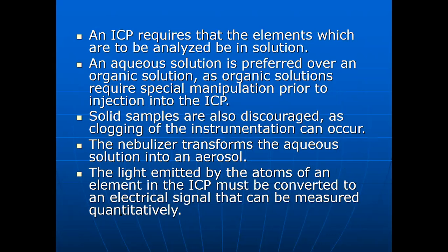Inductively coupled plasma requires that the elements to be analyzed are in solution. For a particular analysis, we should confirm that the particular element is present. An aqueous solution is preferred over an organic solution. While using inductively coupled plasma, we should go only for aqueous solutions rather than organic solutions, as organic solutions require special manipulation prior to injection. If you want to use organic solutions, we have to dilute or add some other solution. It is very difficult, so instead we go for aqueous solutions.